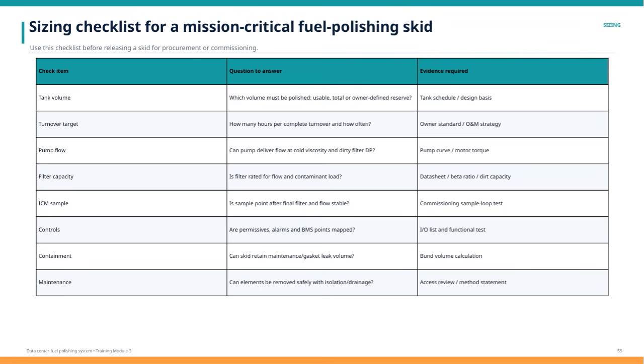Then evaluate the pump flow. It's critical that the pump can deliver the necessary flow even under challenging conditions, such as at cold fuel viscosity and when the filter is dirty, which causes differential pressure. Check this against the pump curve and available motor torque. Filter capacity is another key factor. The filter must be rated to handle the expected flow and contaminant load, which can be confirmed through datasheets, beta ratio, and dirt capacity ratings. For sampling, ensure there is an ICM sample point located after the final filter and that flow conditions at this point are stable. This can be verified during commissioning via sample loop tests.